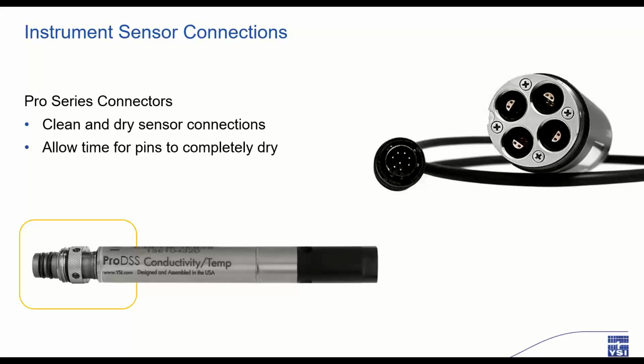Make sure to allow ample time for the port to dry once it has been rinsed before reinstalling the sensors. If you rinsed with alcohol, 15 minutes should be sufficient for drying. Otherwise, allow a couple hours to be sure that the connector is good and dry before installation. The double O-rings on the base of the ProDSS sensors need to be inspected also. Wipe them down with a lint-free cloth and make sure that there's no debris around the O-ring. And then a little dab of Krytox grease on your fingertip applied until they glisten and you're raring to go. Once the ports are clean and dried and your sensors' O-rings are properly lubricated, installing these sensors will create a waterproof connection. Be careful during this process that you do not damage the connection pins. This may result in costly repairs and unwanted instrument downtime.